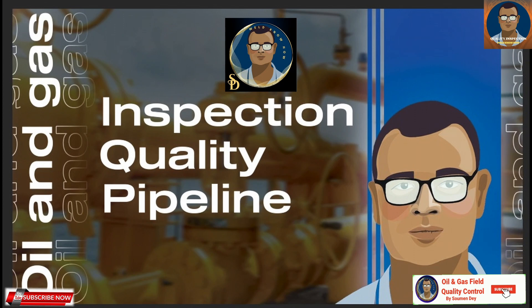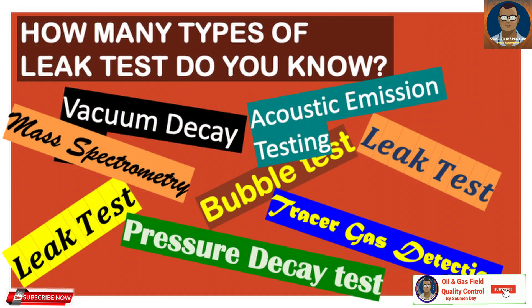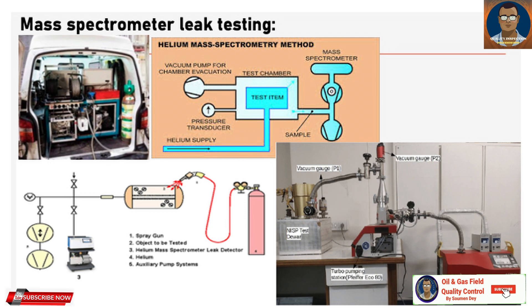Hello knowledge seekers, this is Shoman from Oil and Gas Field Quality Control. Nowadays we are discussing about leak testing. In the last video we discussed about the helium sniffer testing — if you have not listened to it, please go through it. This video runs on the same principle: mass spectrometer leak testing, which is a way to detect very small leaks across a pressure boundary using helium gas.